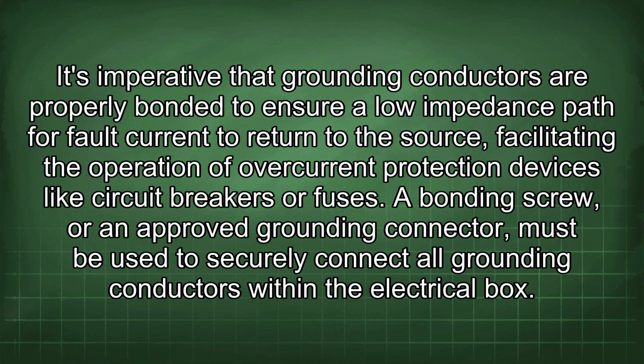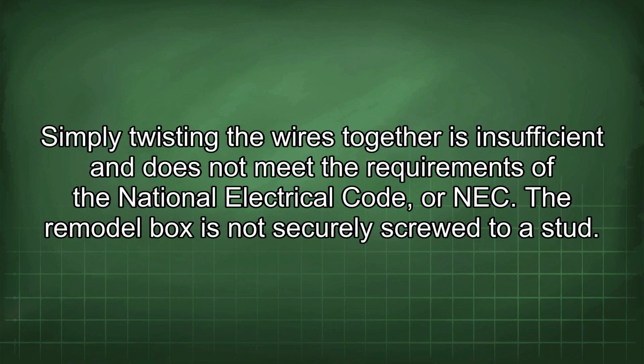the source, facilitating the operation of overcurrent protection devices like circuit breakers or fuses. A bonding screw, or an approved grounding connector, must be used to securely connect all grounding conductors within the electrical box. Simply twisting the wires together is insufficient and does not meet the requirements of the National Electrical Code, or NEC. The remodel box is not securely screwed to a stud.